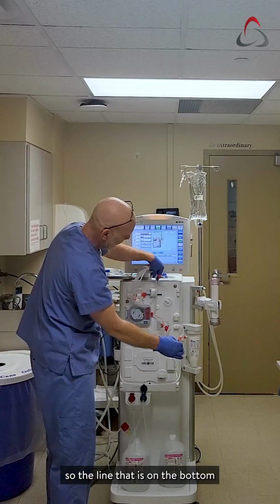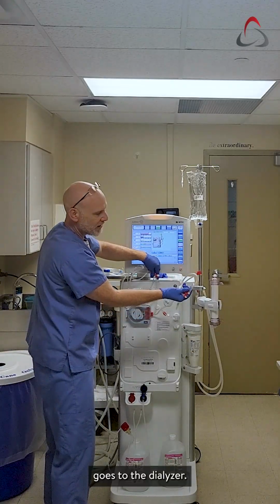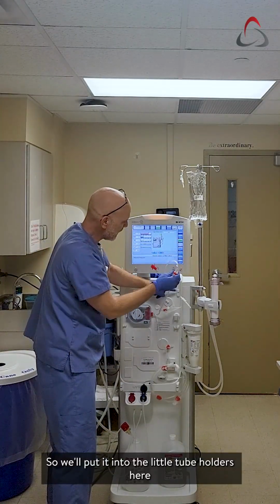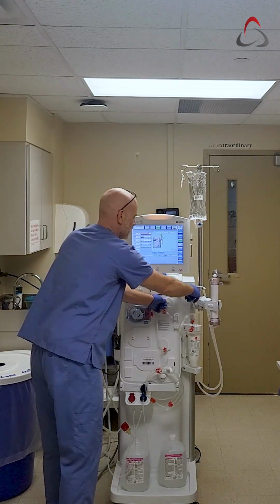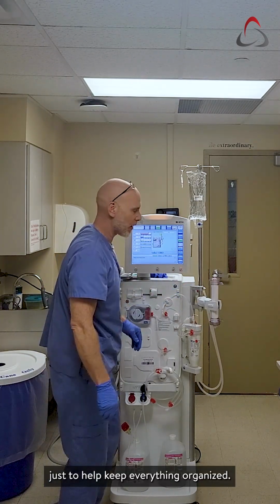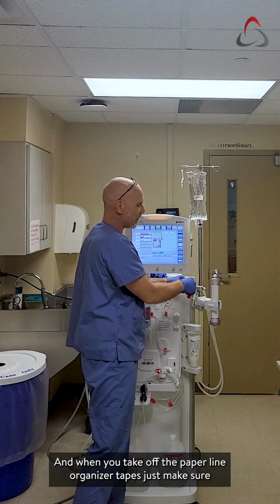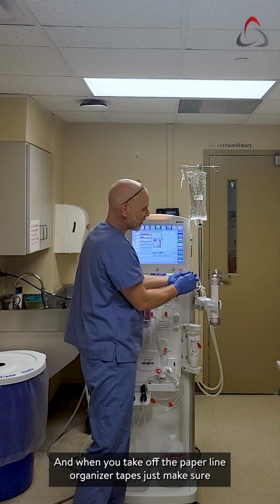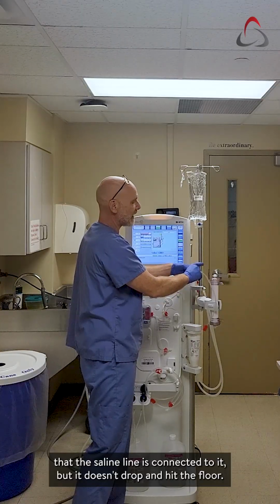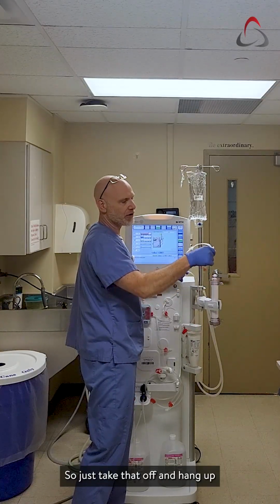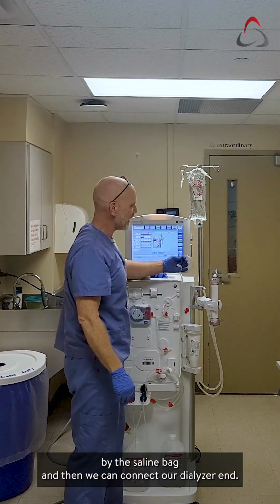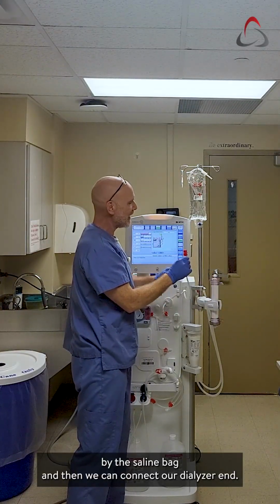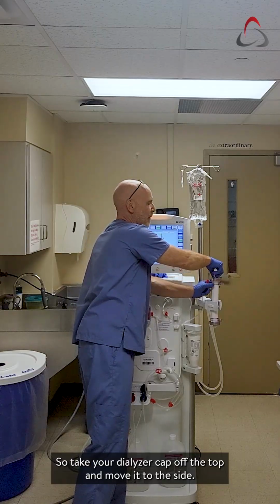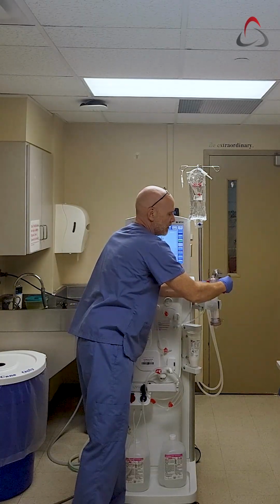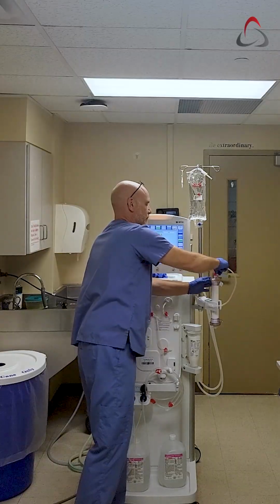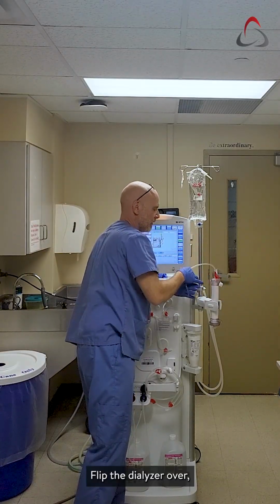So the line that is on the bottom goes to the dialyzer. So we'll put it into the little tube holders here, just to help keep everything organized. And when you take off the paper line organizer tapes, just make sure that the saline line is connected to it, that it doesn't drop and hit the floor. So just take that off and hang up by the saline bag. And then we can connect our dialyzer end. So take your dialyzer cap off the top and move it to the side. And flip the dialyzer over.